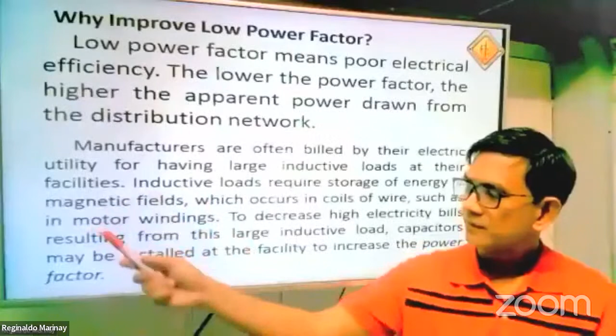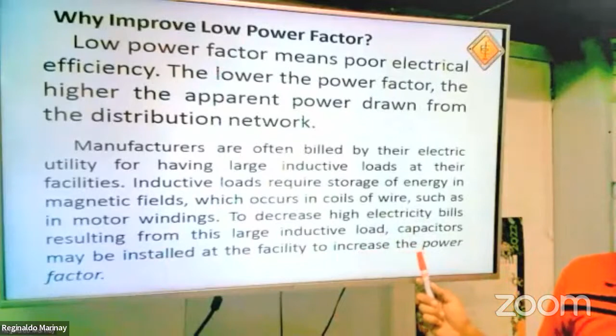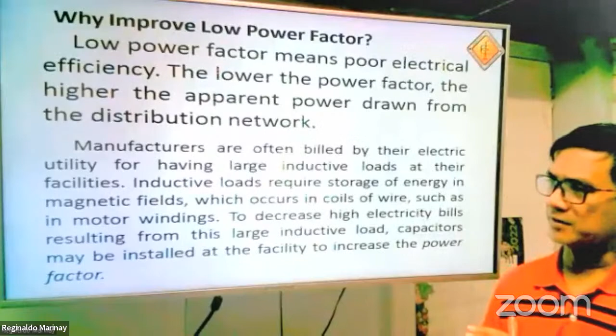For the magnetic field to be maintained, we need the reactive power. That is its function, and it occurs in the coils of the wire, such as in motor windings. If there are motor windings or coils, there are magnetic fields. To decrease high electricity bills resulting from this large inductive load, capacitors may be installed at the facilities to increase the power factor. This is the remedy for low power factor.